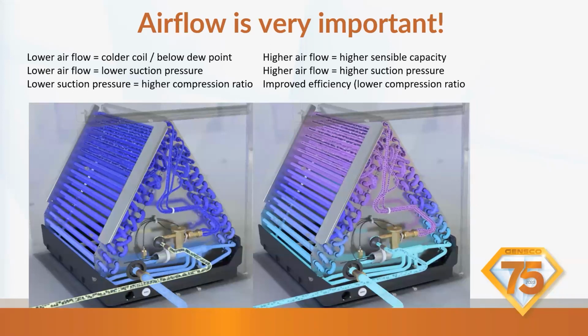And then if we're restricted, we could be icing up the coil too. So first time, whenever I hear of an icy coil, we've got to confirm that we have the 10-degree subcooled charging, and we have to confirm that we have proper airflow. And normally it's one of those two.